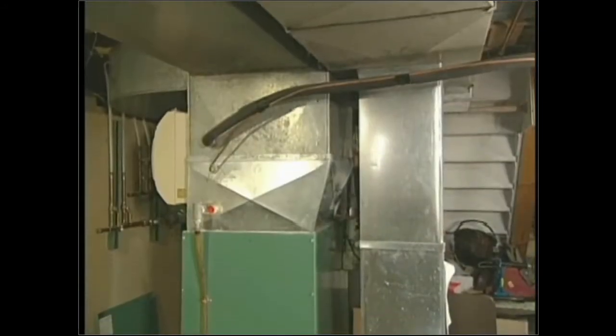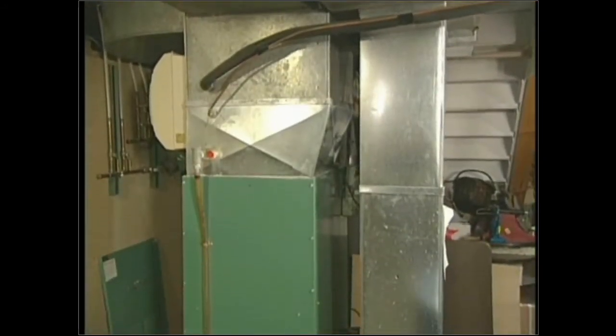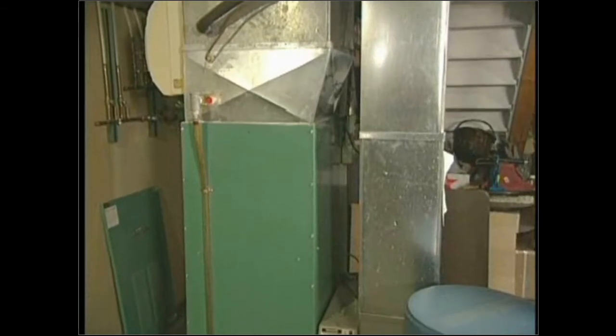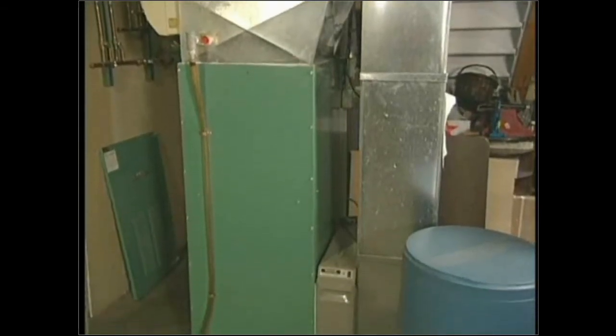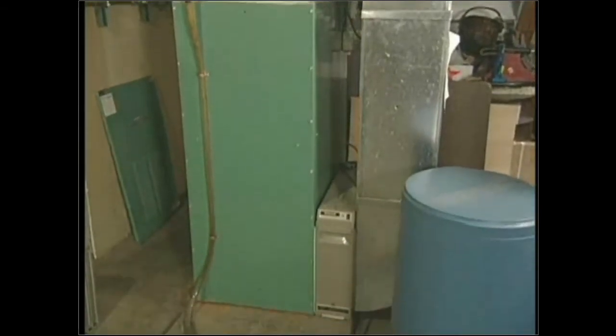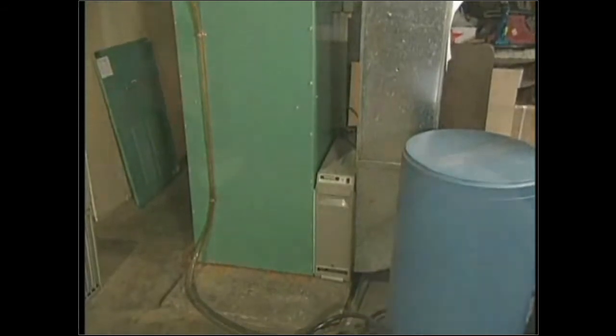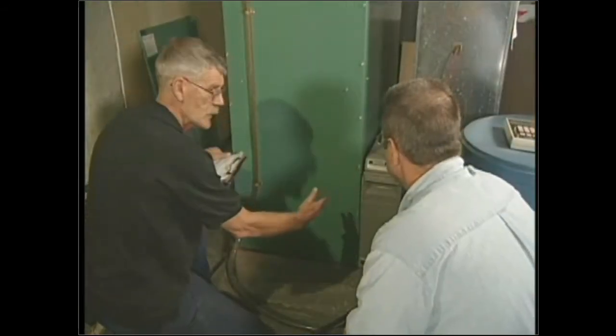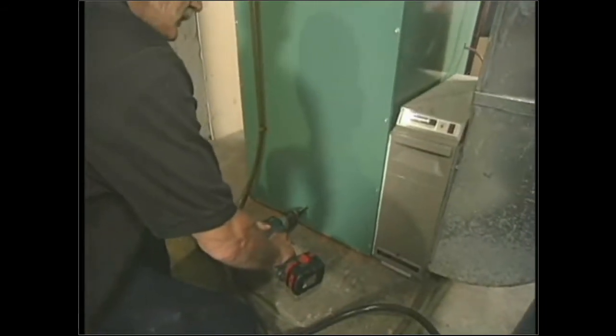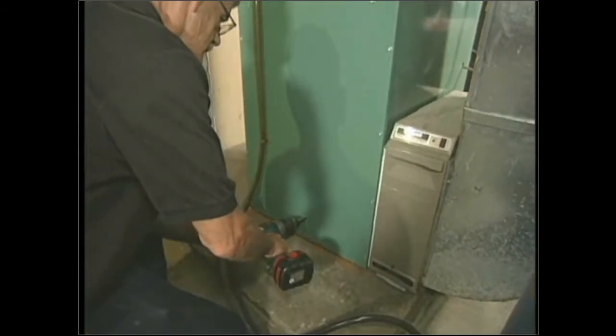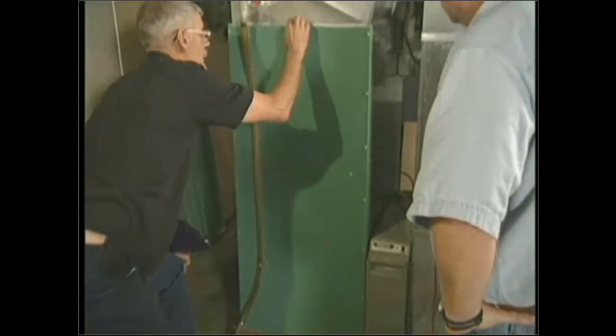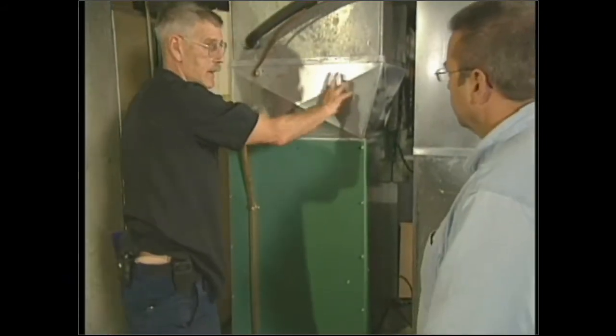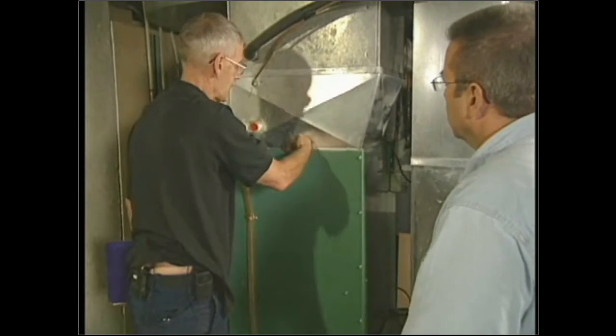We have to locate a point between the air handler and the filter. Oh, I remember that from the gas furnaces. That's what you wanted, but there wasn't any ductwork there to drill into, and it looks like the same situation here. So we had to go up and talk to the homeowner, get permission to drill the unit. We drilled a hole here, which is between the air handler and the filter. And then we drilled one here, which is a little bit different because we have an A-coil here.